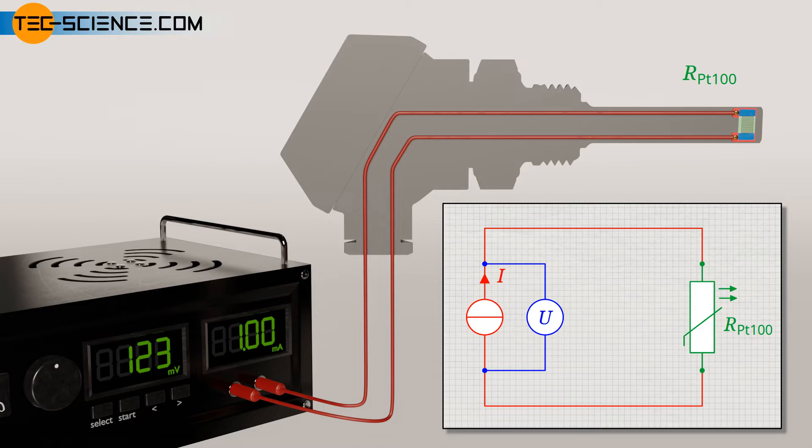This measuring principle is also referred to as two-terminal sensing, since only two measuring leads are sufficient for measurement. In a simplified view, the resistance value of the PT100 can now be calculated from Ohm's law as the quotient of voltage and current.